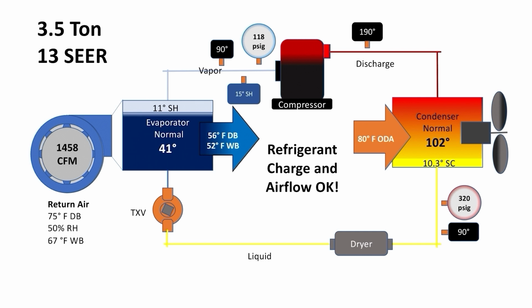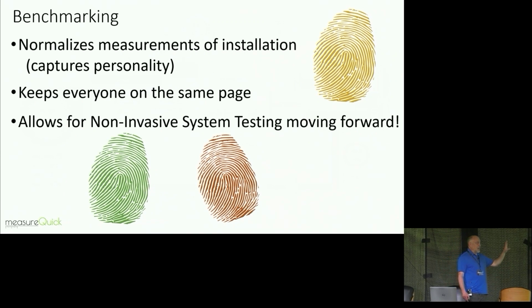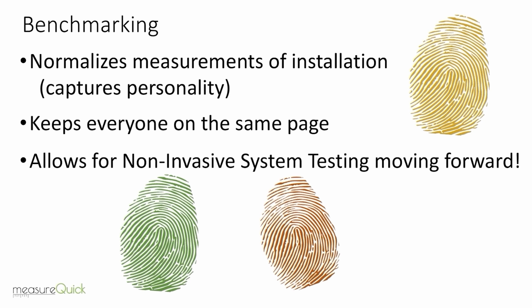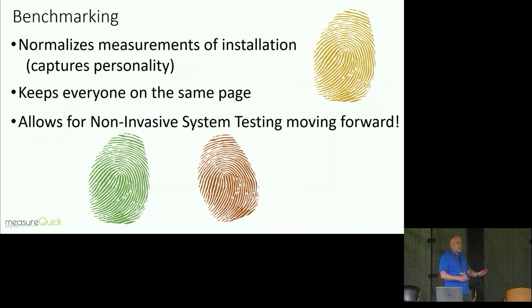So once we get the charge right, we get the airflow right, we get everything dialed in the way we want it, right? Then what we're doing is we're capturing all the design temperature differences, the refrigerant charge, everything about that system, static pressure, model numbers, serial numbers, so that we can do non-invasive testing going forward, right? The whole idea behind this is we never need to hook up gauges to a system again.